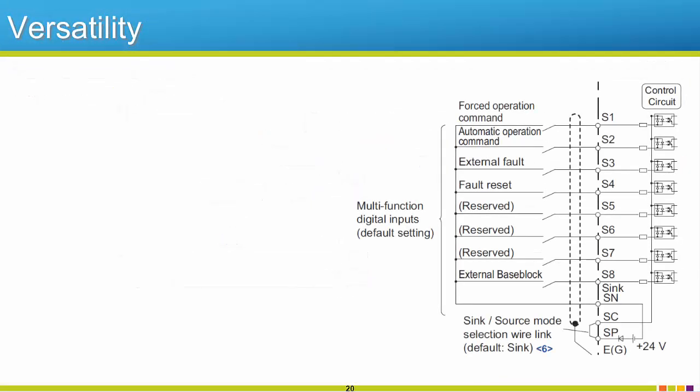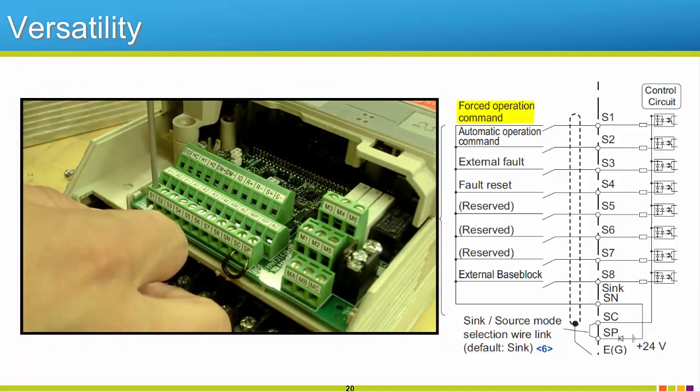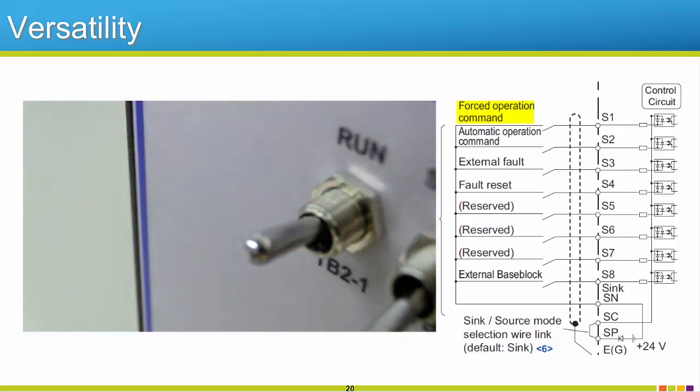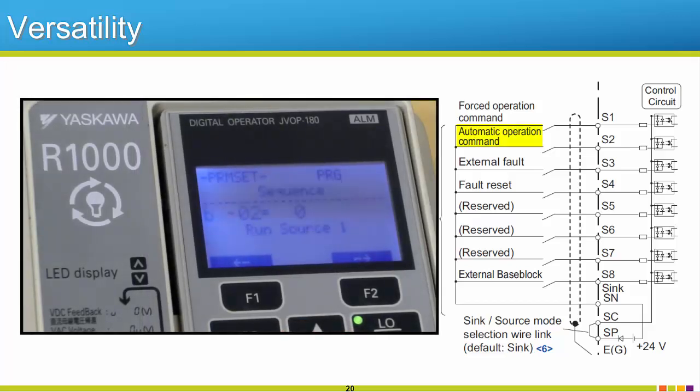The R1000 sequencing can be integrated into any new or existing application. A systems integrator can opt to wire a forced or an automatic operation command. A forced command will manually start the regen unit operation. The automatic command can be considered a little bit more intelligent as it will activate and deactivate the R1000 as the DC bus voltage increases or decreases. So it will only be operating when the application is in a regenerative state.